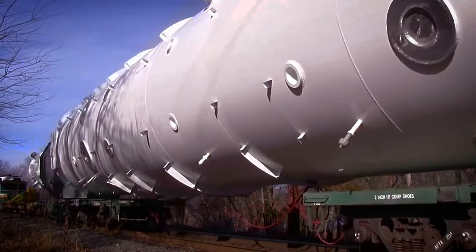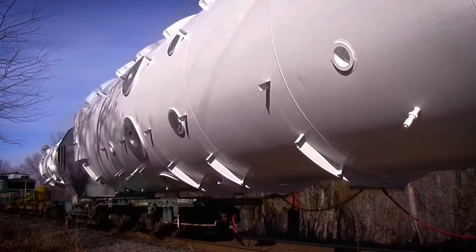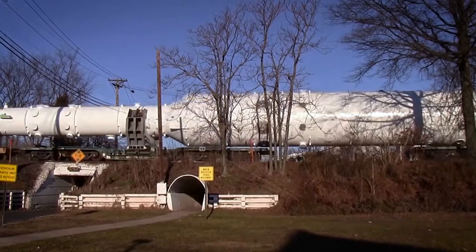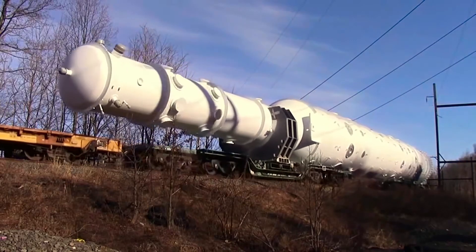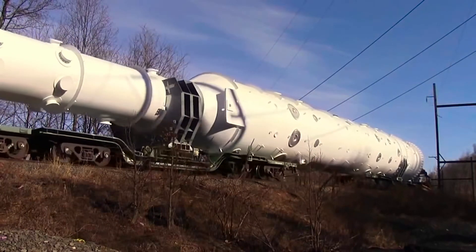Those wound tubes can provide a heating surface as great as 40,000 square meters. These units are compact, but they're big — one might weigh over 250 tons and look like a gigantic spark plug, or maybe like a Saturn rocket. We can build these units for all kinds of fluids, pressures, and temperature ranges. They transfer an amazing amount of heat in a given space.